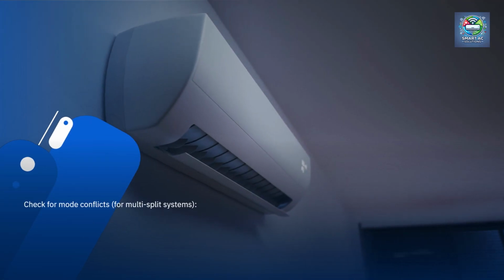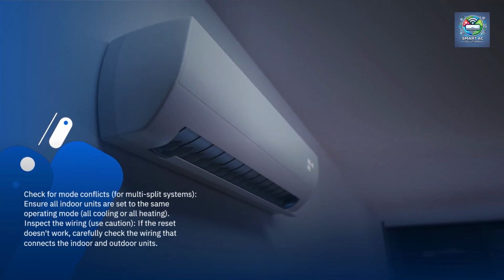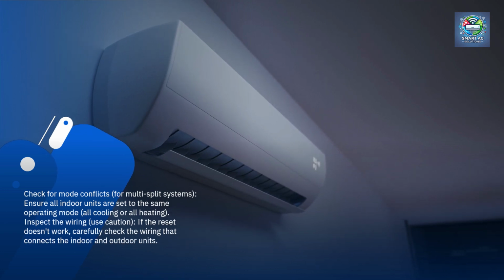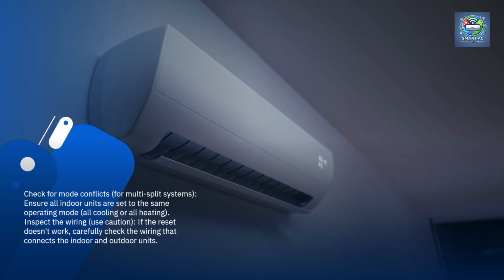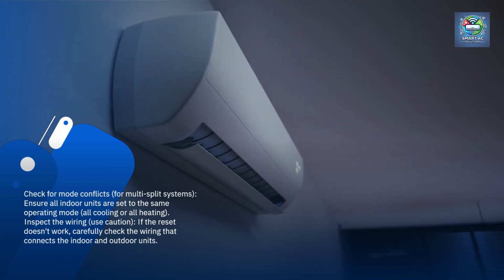Check for mode conflicts. For multi-split systems, ensure all indoor units are set to the same operating mode, all cooling or all heating.